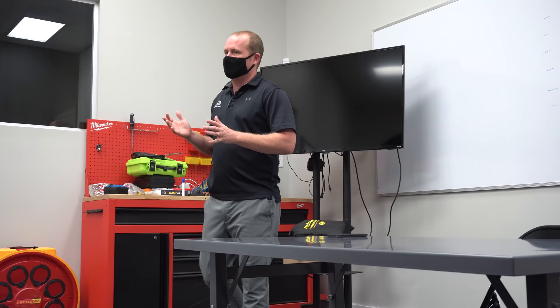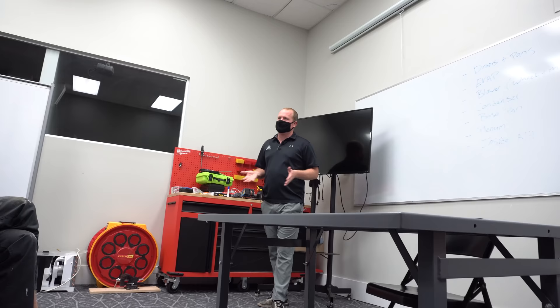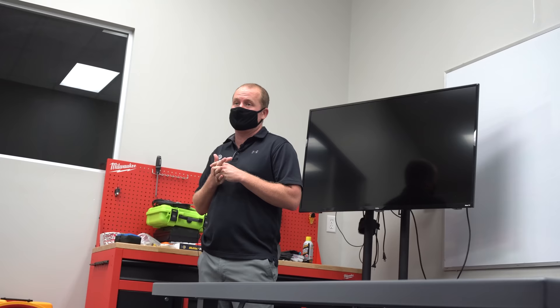Some people use a Panduit strap or something similar to get the gunk out of the drain pan and rinse it out with water. On a maintenance, service call, or when charging a customer for a drain line cleaning, we never just do the drain line. On an install it's a brand new drain pan so the drain line is your focus, but on service calls and maintenances, you need to be focused on the drain pan as well. Use your pump sprayer in stream mode to force water from the back. Depending on the application, clean the drain pan and drain line until it's actually clean — visually verify with your flashlight.